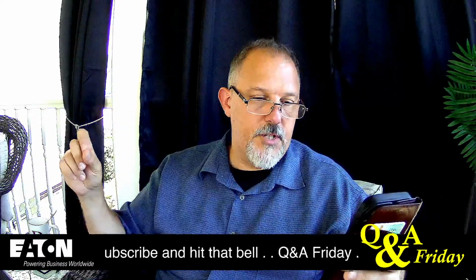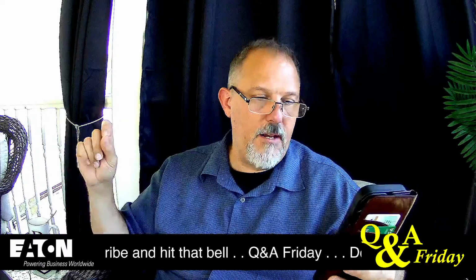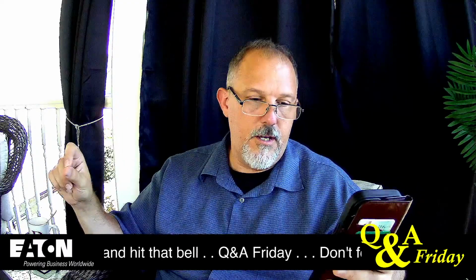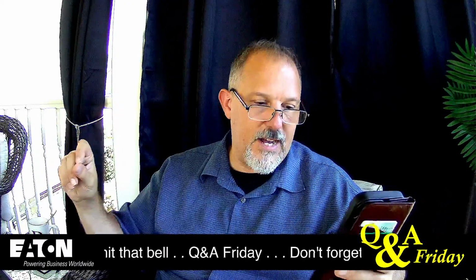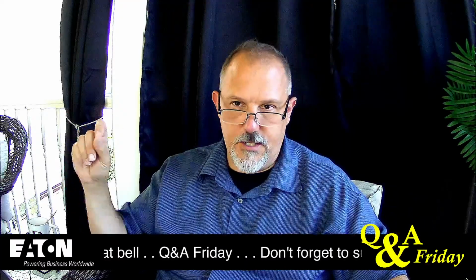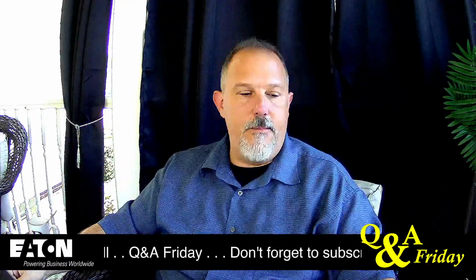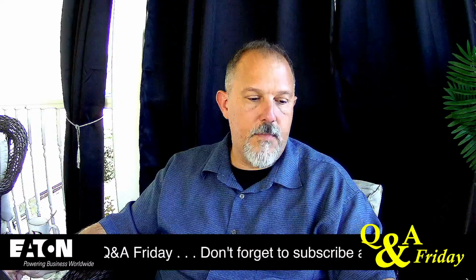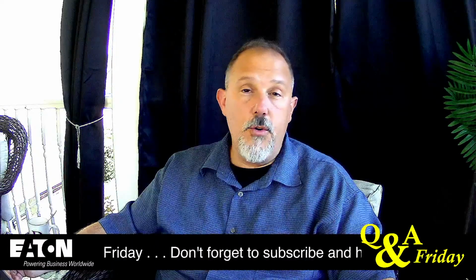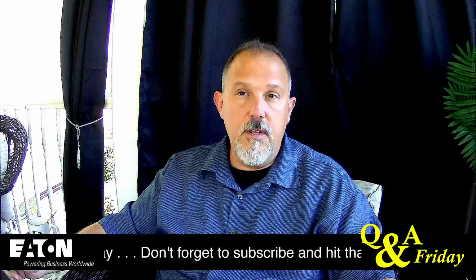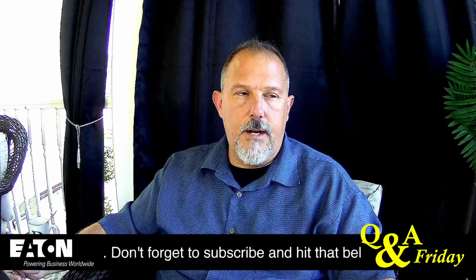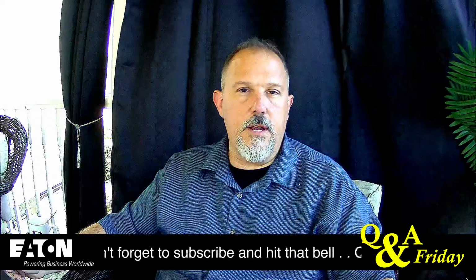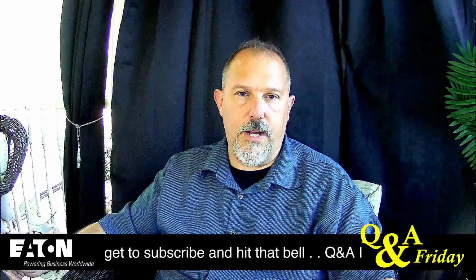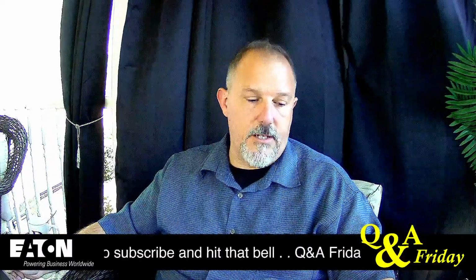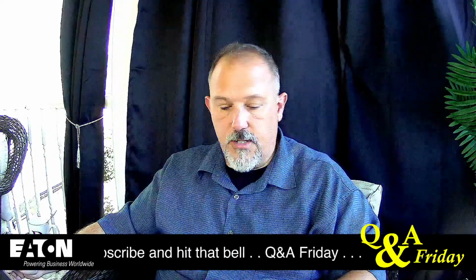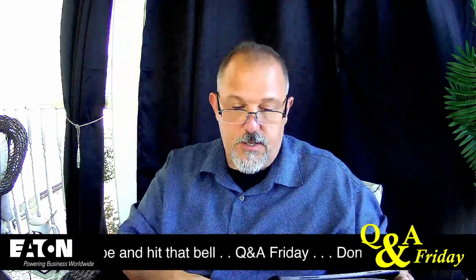Is that a correct assumption, given how most MCC main breaker sections are constructed? Are there MCCs that provide full isolation? Oh man, Mr. D, that's a toughie. Now, here's my thought process. You are taking the conservative approach, and I think that's good, because you're providing a little bit more margin. The moment you start to get into the discussion of whether or not there's a line side barrier, okay, here's the issue that you'll come across.